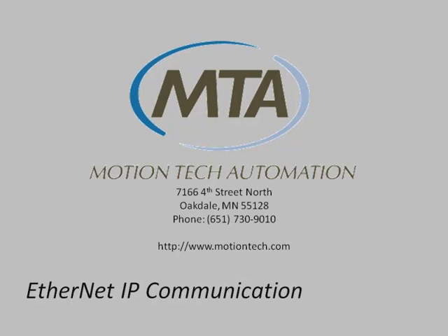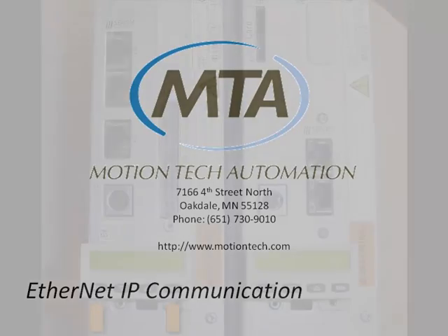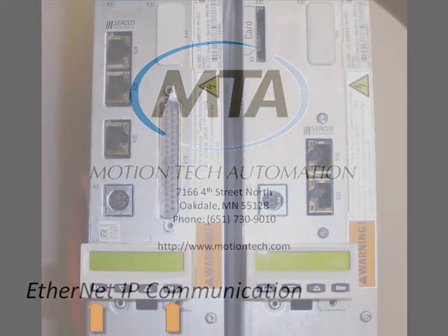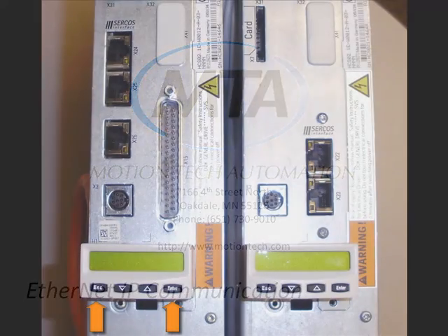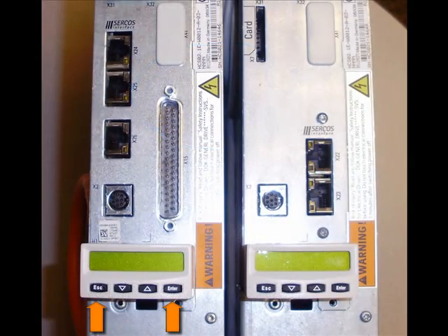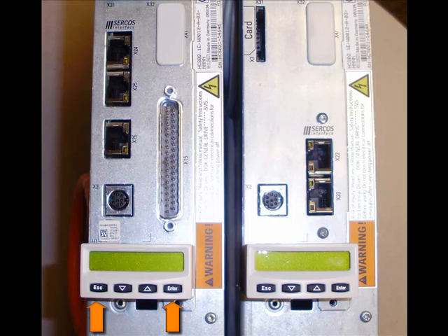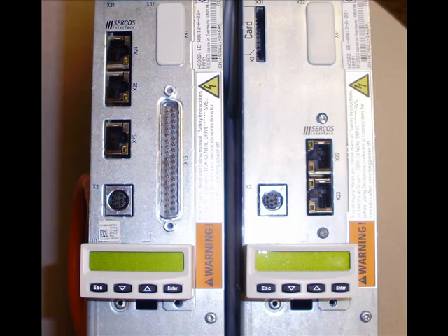For our drive setup, we'll be using Bosch's IndraWorks software for our drive commissioning. The first step in setting up the IndraDrive to communicate by Ethernet IP is to set the drive IP address. This can be done with the drive powered up, pressing the outside two buttons of the control panel for approximately 8 to 10 seconds to get into the menu system.